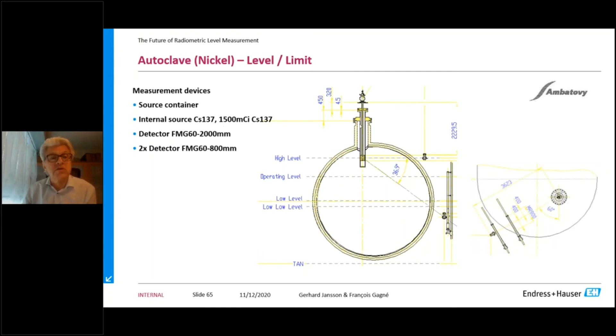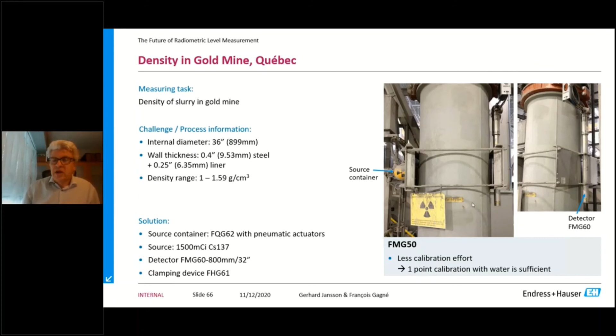This is a gold mine in Quebec. You can see here line sizes of 36 inches. Source container mounting on the outside, and this is also the old detector on the opposite side. To calibrate this with 2 known liquids like water and a slurry is quite an adventure to try to do. So if you can now just fill this pipe with water, have it free without anything, and do this one point calibration, it will save them a lot of effort in that case.